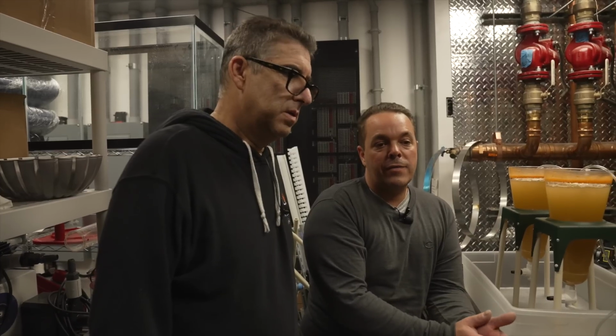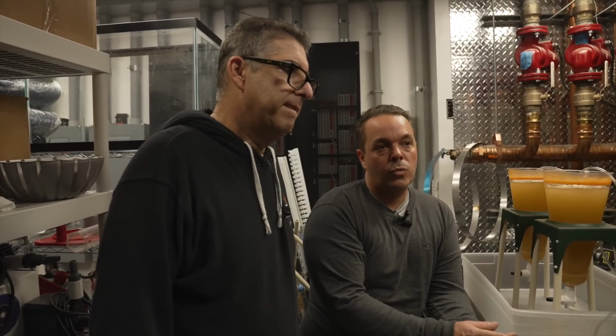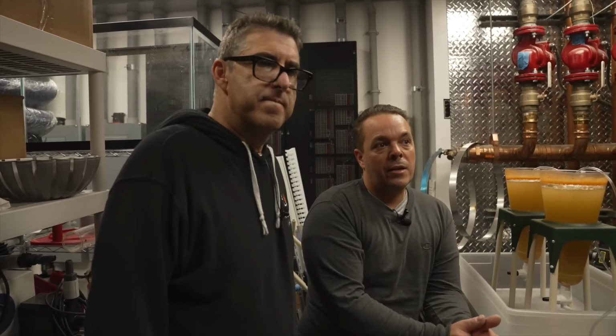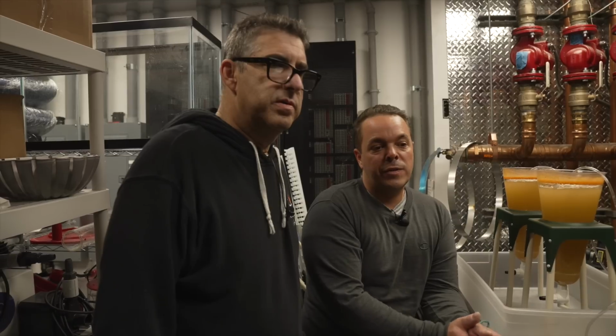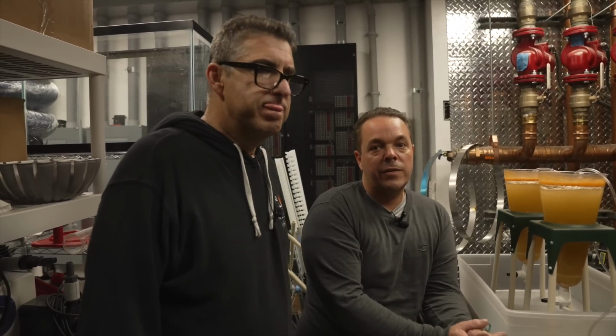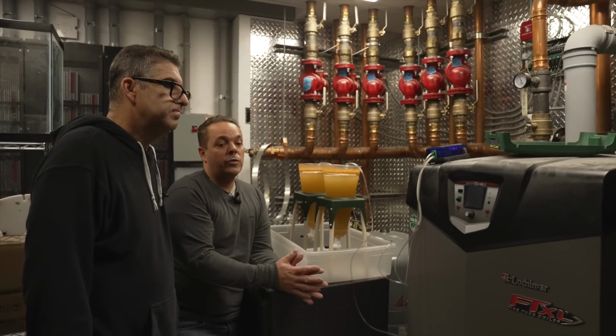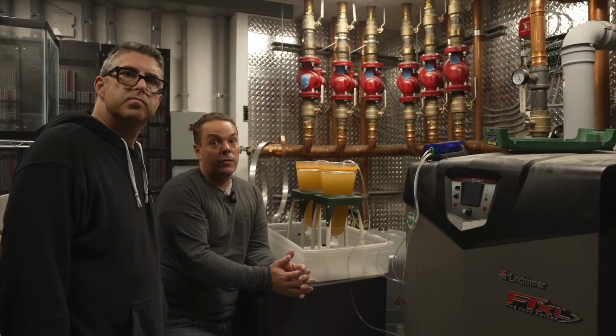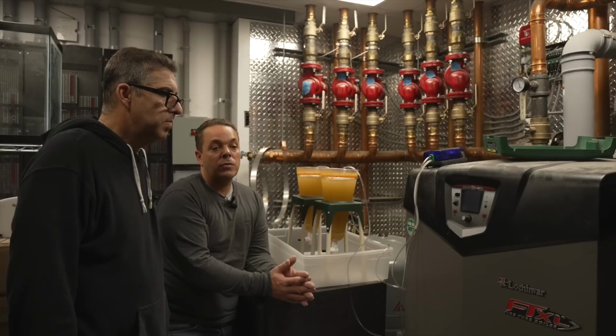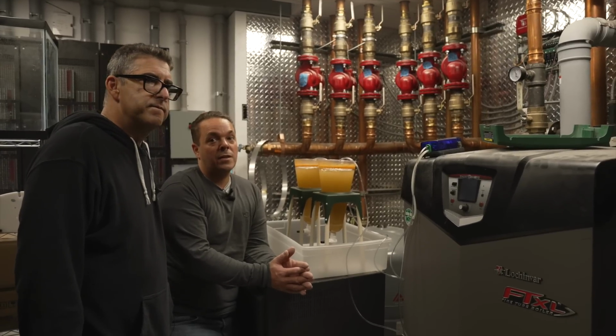The 5,000 gallon water change tank is the one we use primarily, and we heat groundwater, which is approximately 55 degrees, to the 75 degrees we need to use and make salt water in less than an hour. So 5,000 gallons going up 20 degrees, really in 30, 40 minutes. Just to put this in perspective, we have 1.2 million BTUs for the fish tanks. An average house has 200,000 BTUs to heat the entire house.